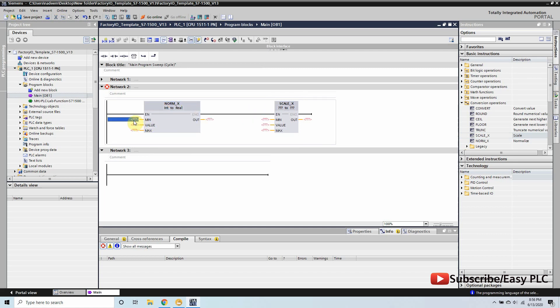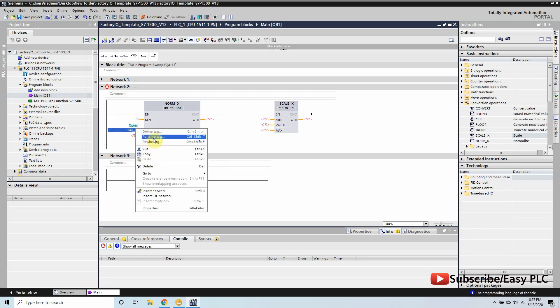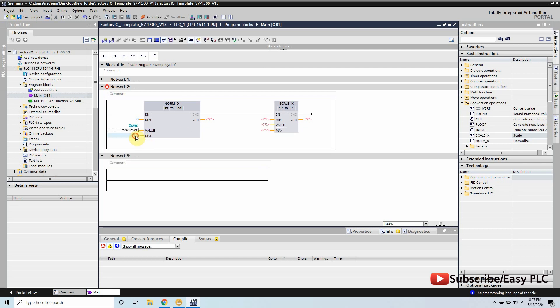As we all know, the NORM_X function is used to convert the analog level input values to real numbers from 0.0 to 1.0, and the SCALE_X function converts these real values to the minimum and maximum range given in the SCALE_X command. IW30 is the input address of the analog level transmitter used in this tank.